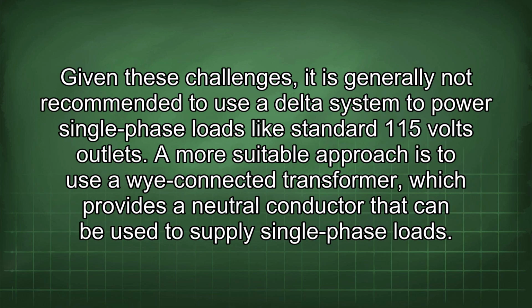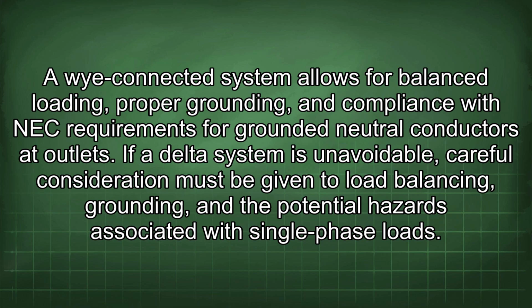Given these challenges, it is generally not recommended to use a delta system to power single-phase loads like standard 115 volts outlets. A more suitable approach is to use a Y-connected transformer, which provides a neutral conductor that can be used to supply single-phase loads. A Y-connected system allows for balanced loading, proper grounding, and compliance with NEC requirements for grounded neutral conductors at outlets.